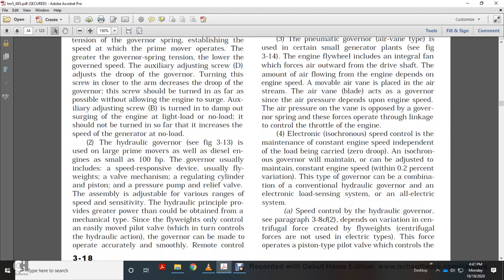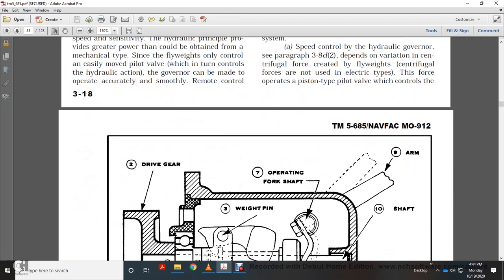The isochronous governor will maintain constant engine speed to within two-tenths of a percent variation. This type combines a conventional hydraulic governor with an electronic load sensing system. The speed control hydraulic governor, per paragraph 3.8.D, uses centrifugal force created by flyweights. Centrifugal force is not used in the electrical type. The force operates a piston-type pilot valve which controls the system.